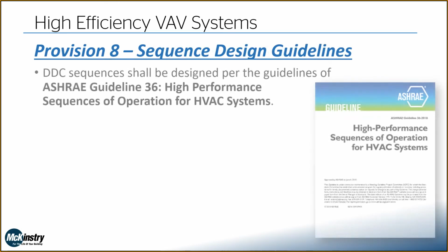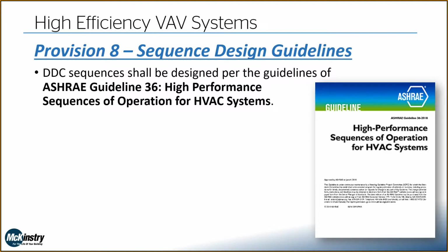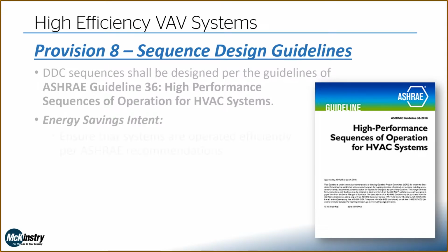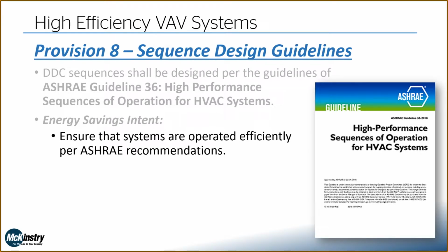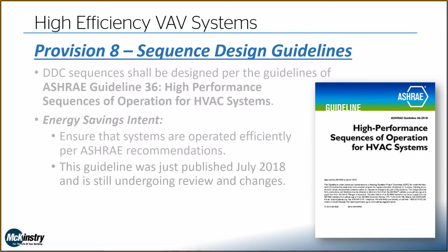Sequence design guidelines. Your DDC sequences shall be designed per the guidelines of ASHRAE Guideline 36, High Performance Sequences of Operation for HVAC Systems. The intent here: let's just make sure our systems are operated efficiently per ASHRAE recommendations.